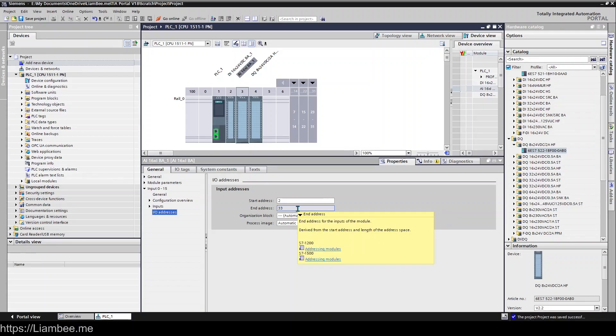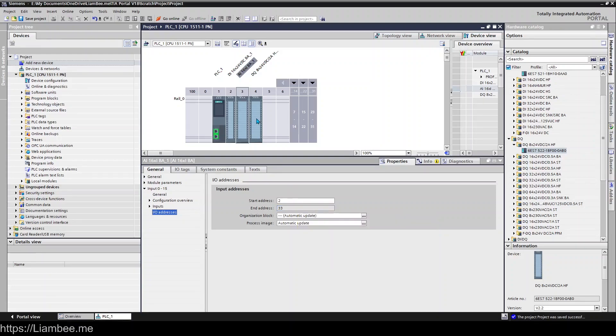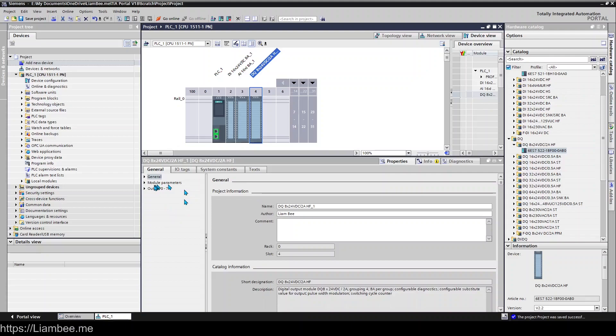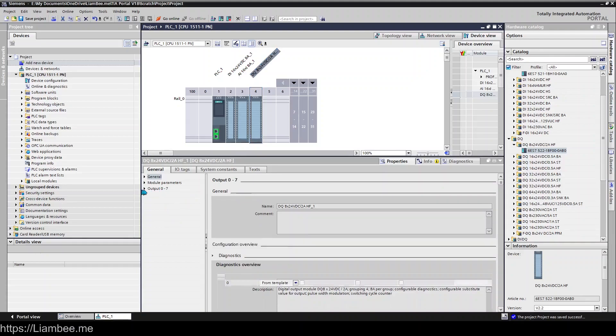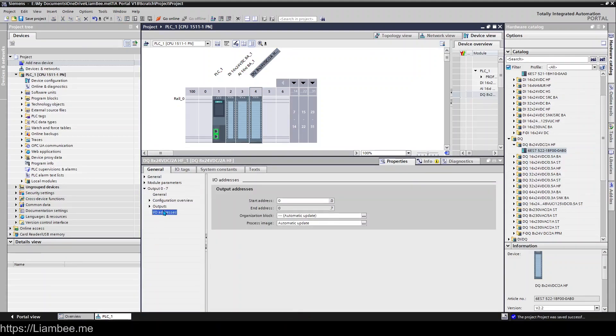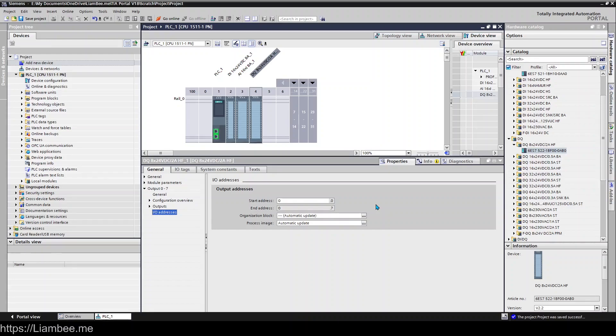When it comes to outputs we have the same setup again. I'll make that a little bit bigger and come down here. This one's starting at zero and ending at 0.7, which you'll notice is the same as the digital inputs, but digital input is using I for input and digital output is using Q for output. Siemens have always used I for inputs and Q for outputs. Some of the PLCs might use O for outputs, but Siemens uses Q.